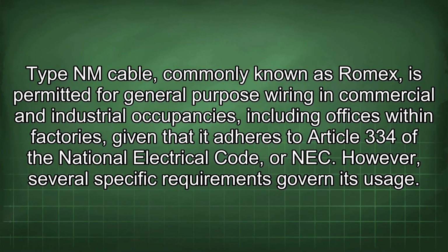Type NM cable, commonly known as Romex, is permitted for general-purpose wiring in commercial and industrial occupancies, including offices within factories, given that it adheres to Article 334 of the National Electrical Code, or NEC. However, several specific requirements govern its usage.